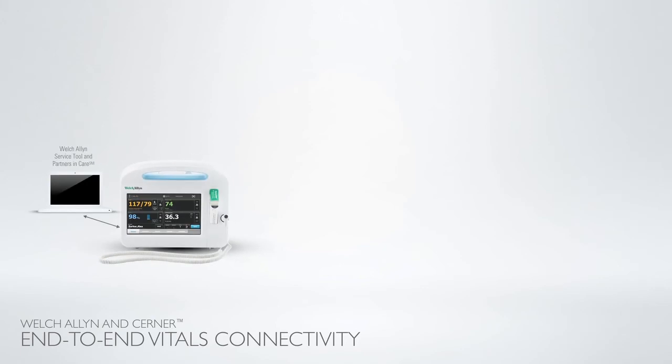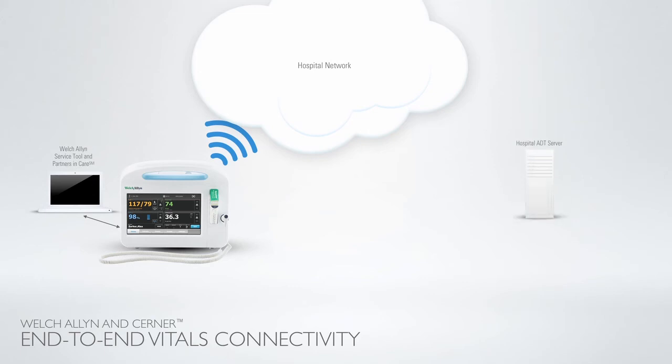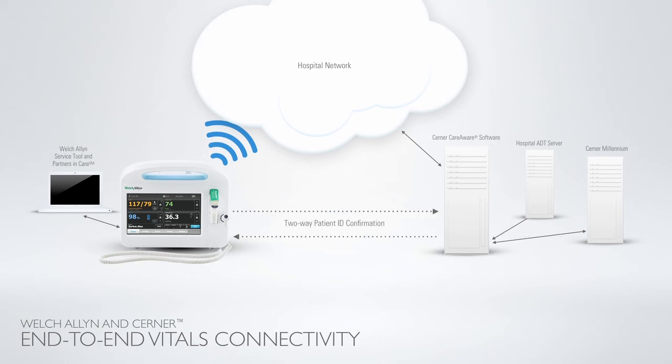The Connex VSM device is flexible, connecting to the server in a wide range of workflows including wireless connectivity that meets the latest 802.11 ABG wireless security standards. We were able to leverage existing infrastructure such as ADT patient registration, Cerner EMR, and CareAware device connectivity. The device bi-directionally communicates directly to CareAware, sending and receiving queries that enable exchange and validation of data — critical for nursing authentication and positive patient ID. After vital signs are taken and the clinician validates the results, data is sent directly from the device to CareAware using the Cerner VitalsLink application.